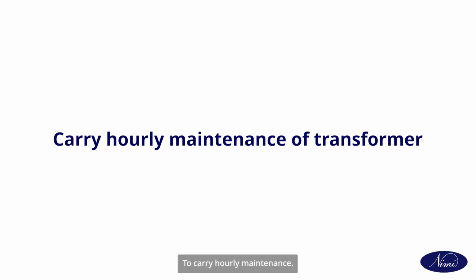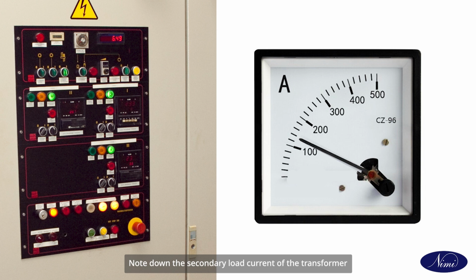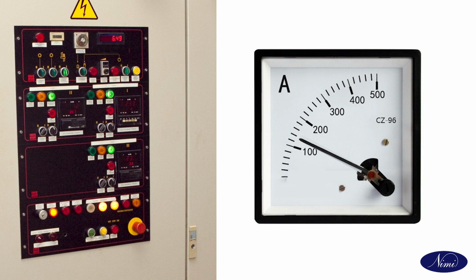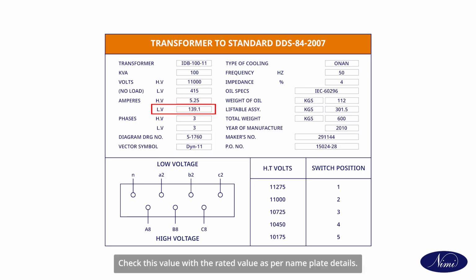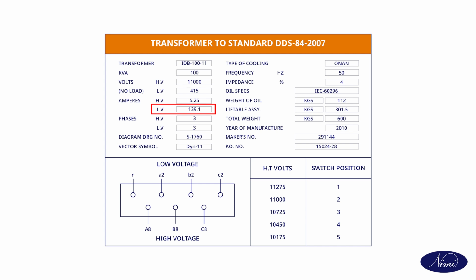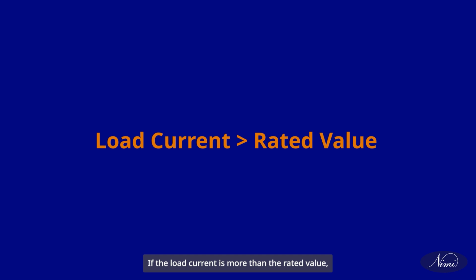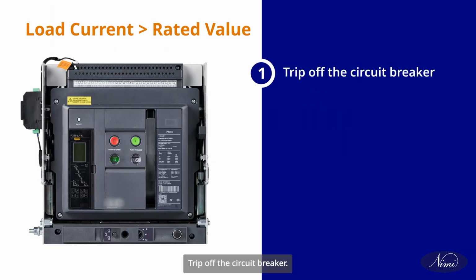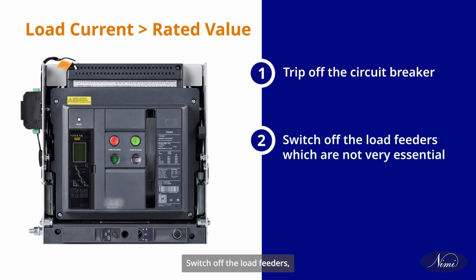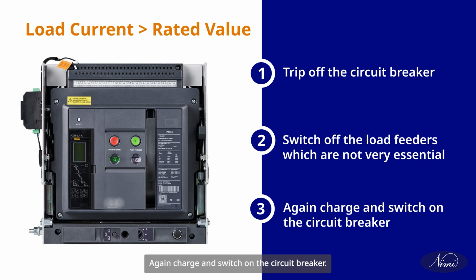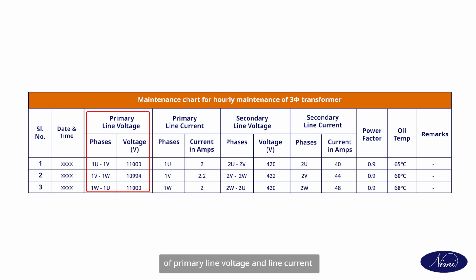To carry out hourly maintenance, note down the secondary load current of the transformer in the ammeter provided. Check this value with the rated value as per nameplate details. If the load current is more than the rated value, then reduce the load on the transformer by the following sequence: trip off the circuit breaker, switch off the load feeders which are not very essential, again charge and switch on the circuit breaker. Record the values of primary line voltage and line current and secondary line voltage and line current and power factor in tabulation.